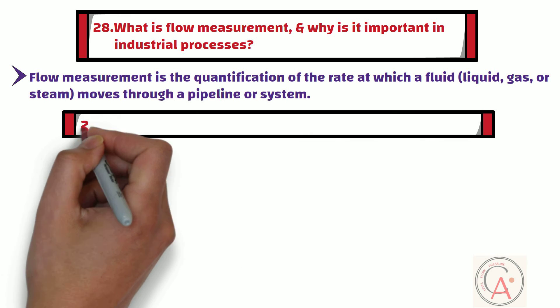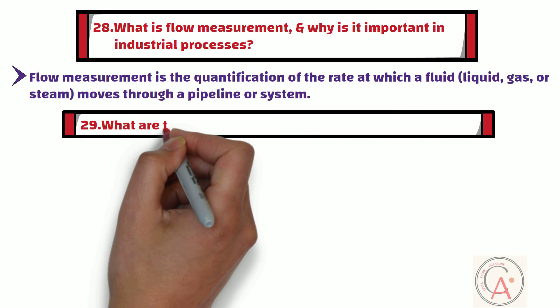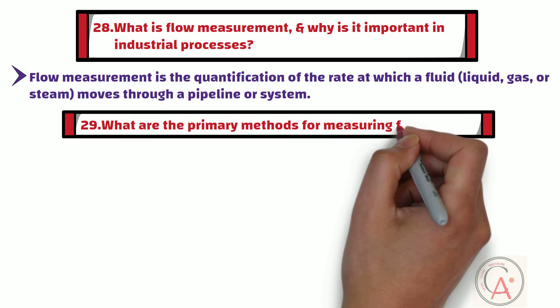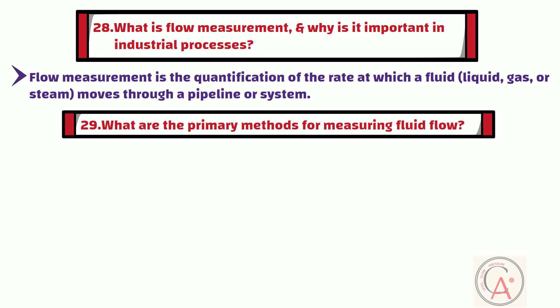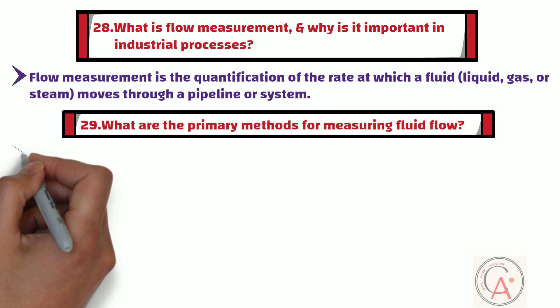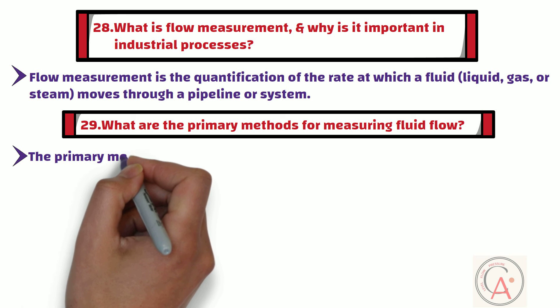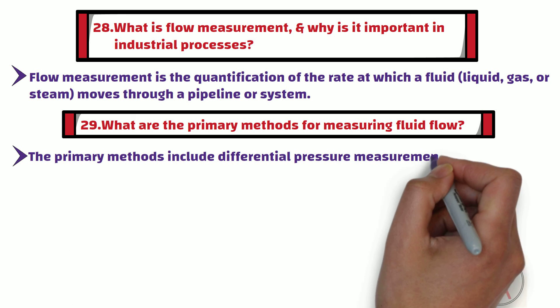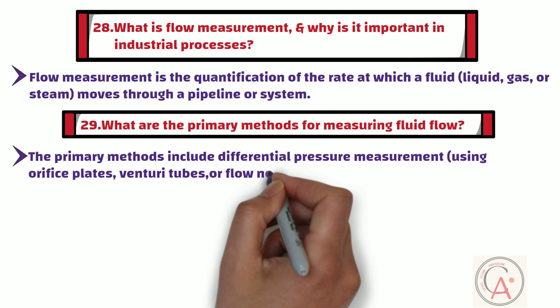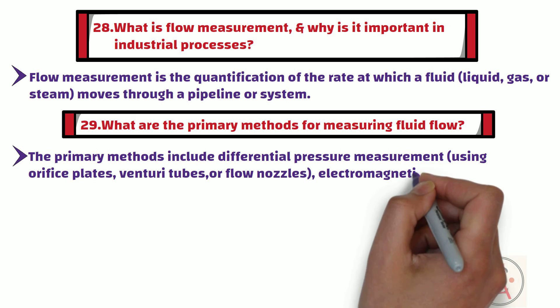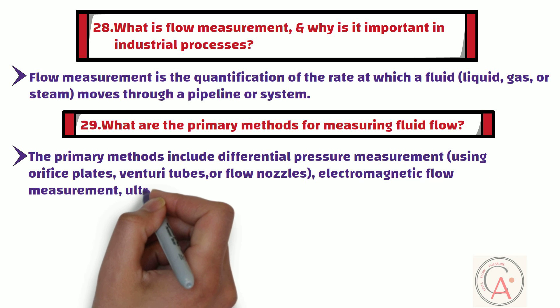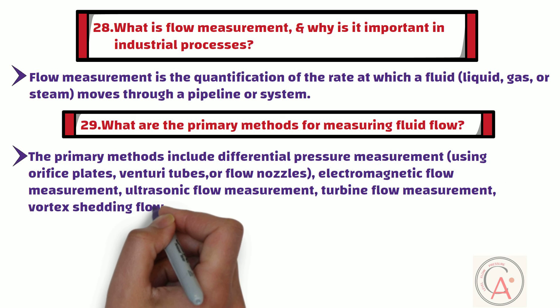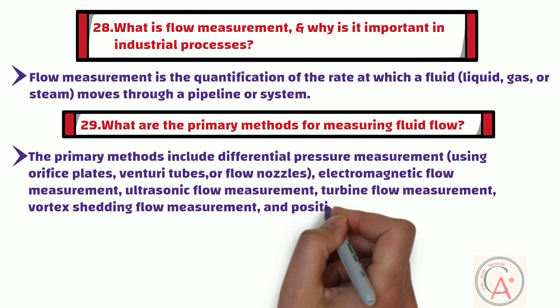The 29th question is: what are the primary methods for measuring fluid flow? The primary methods include differential pressure measurement using orifice plates, venturi tubes, or flow nozzles, and electromagnetic flow measurement, ultrasonic flow measurement, turbine flow measurement, vortex shedding flow measurement, and positive displacement flow measurement.